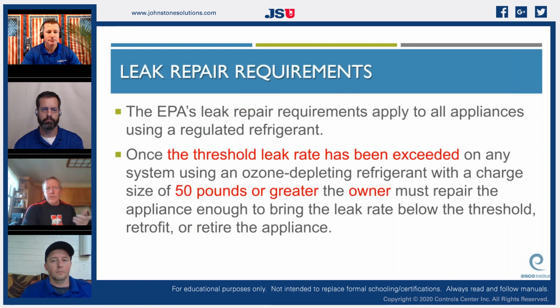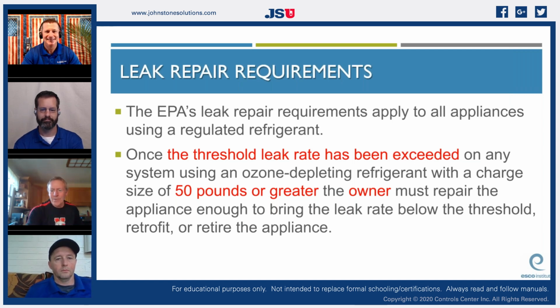Once the threshold leak rate, this is the EPA's requirements for systems holding over 50 pounds. Once the threshold leak rate has been exceeded on any system using an ozone depleting refrigerant with a charge size of 50 pounds or greater, the owner must repair the appliance enough to bring the leak rate below the threshold. I've always been amazed at how they word this. It doesn't sound like they're telling you to fix a leak. They're telling you if it's a 10% leak and you get it down to 8%, you're okay. Isn't that crazy? That's nuts, but fix the leak down to 0%, how's that?